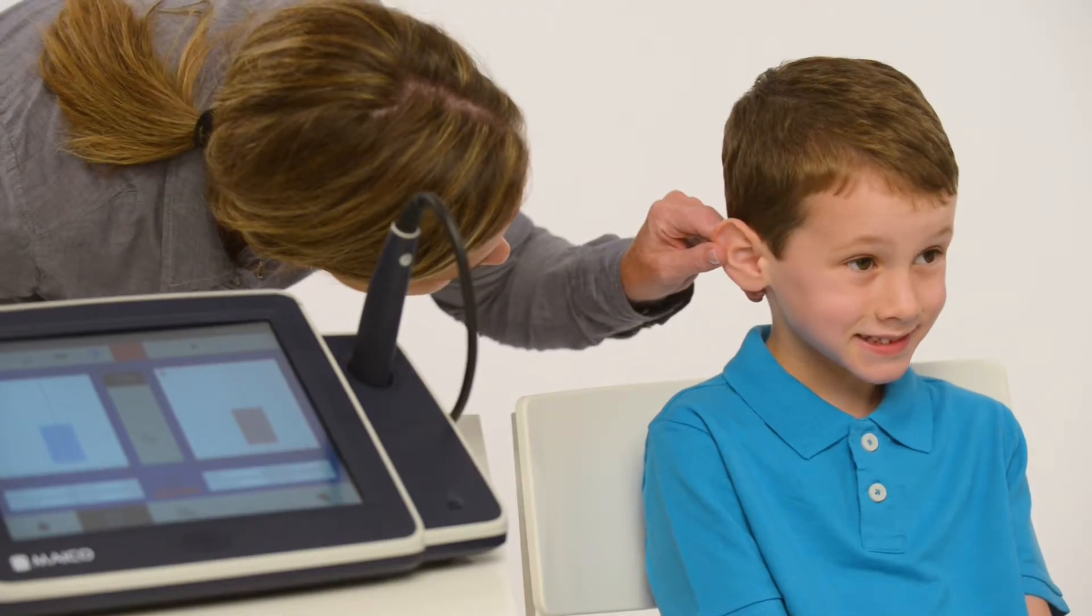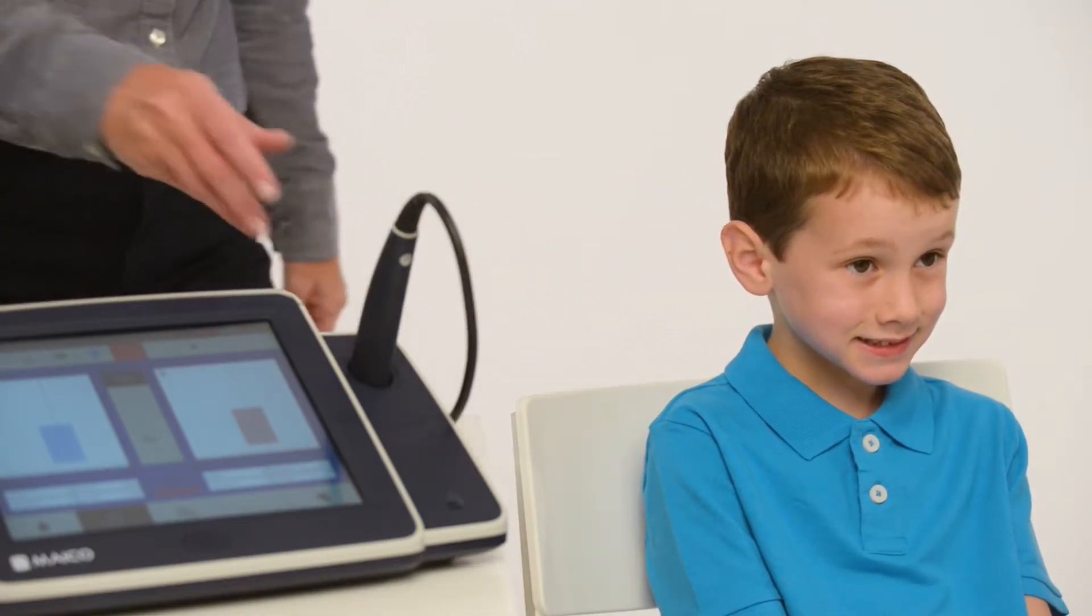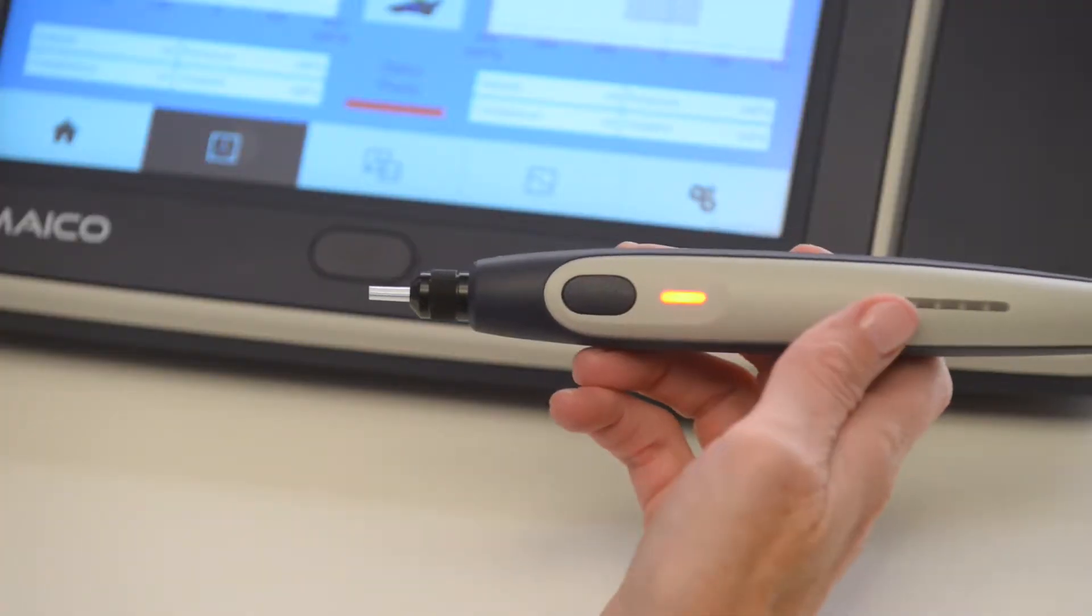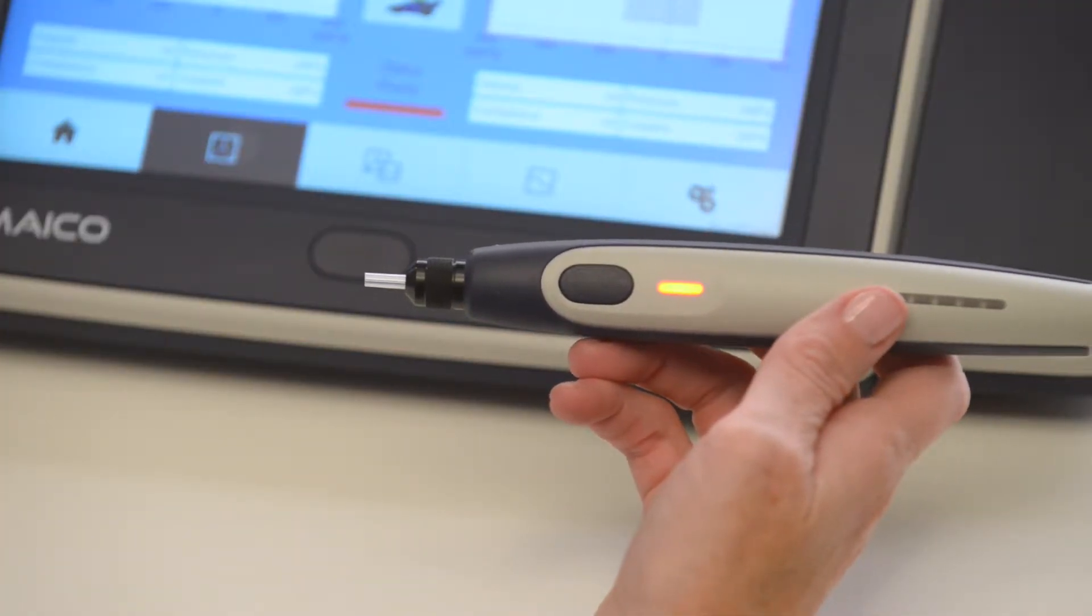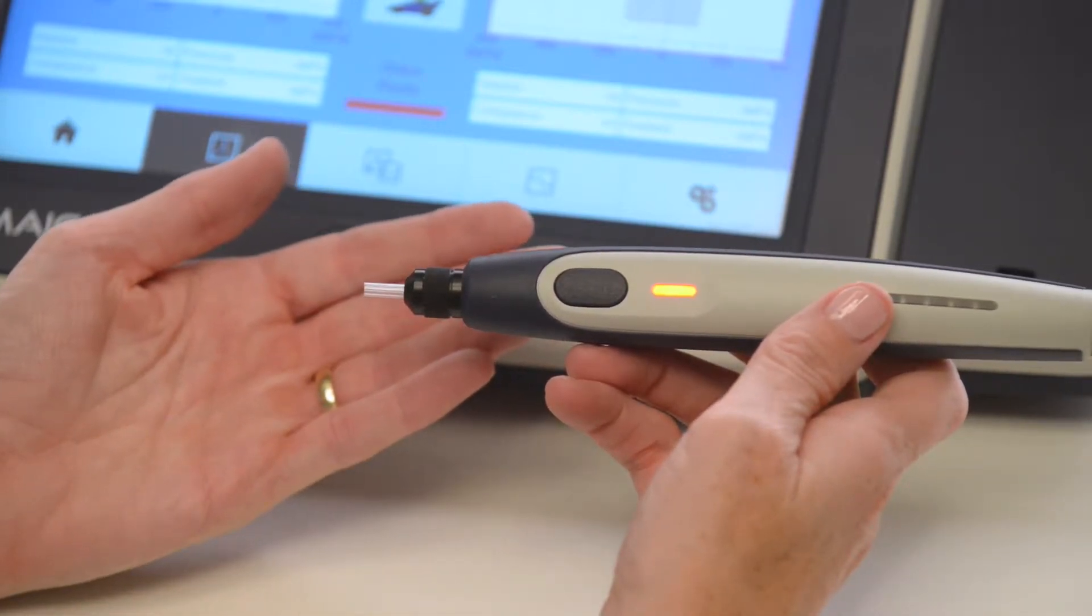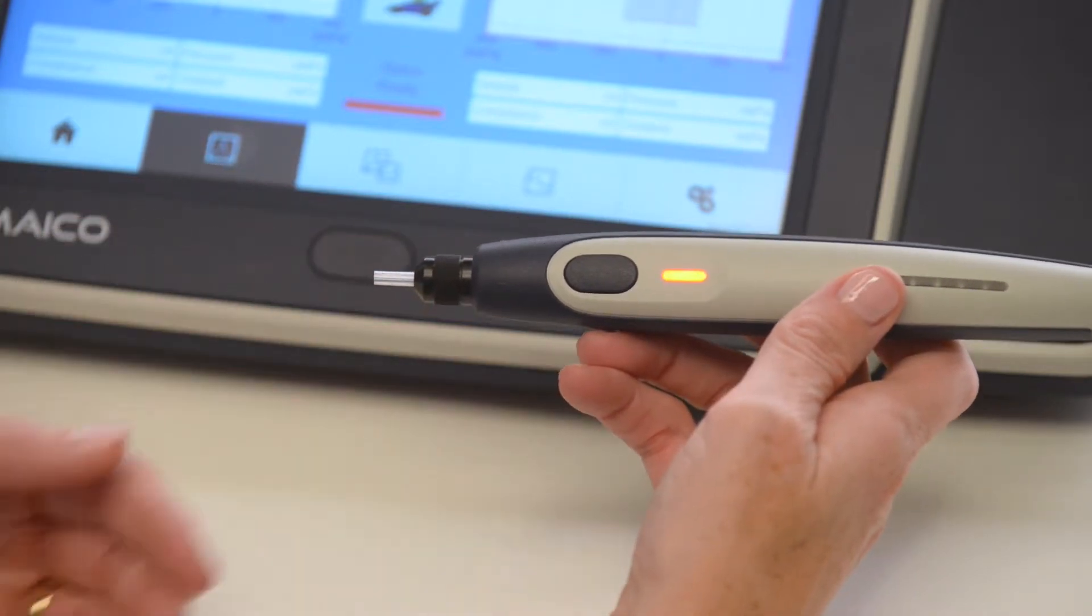When starting a tympanometry test, make a visual inspection of the ear canal to ensure there is no earwax. It is also critical to inspect the probe tip between patients to ensure it is clean and free of debris. If there is an obstruction, clean the probe tip using the tool provided. An occluded probe could result in flat tympanograms and may damage the probe.